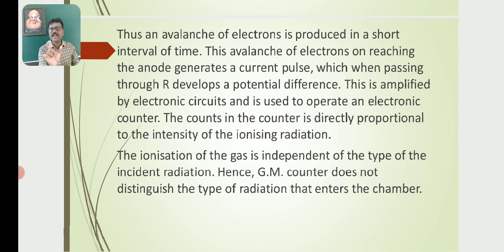So this is a very important sentence. The counts in the counter are directly proportional to the intensity of the ionizing radiation. If the intensity of the ionizing radiation is more, the number of counts in the Geiger-Müller counter is also more.